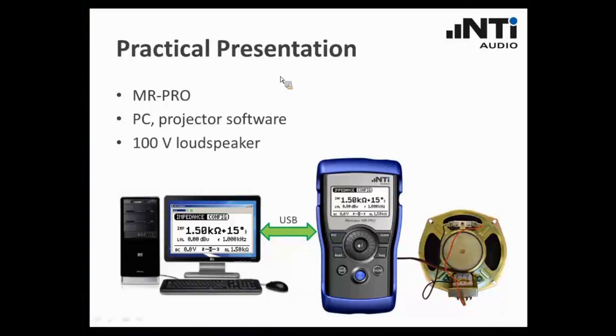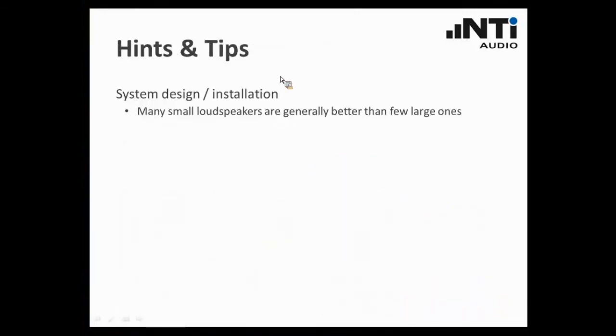I would like to provide you some hints and tips. The first one is when you design or install a system, there is a rule of thumb. Generally, it is recommended to install many small loudspeakers rather than few large ones. The reason is very simple. With a better distribution of small loudspeakers, you usually get a more homogeneous sound field in your venue, instead of having just three or four large and loud loudspeakers. They are more inhomogeneous in the sound field, and that has a negative impact on the speech intelligibility. So realizing a system with a good speech intelligibility would rather require a larger number of small loudspeakers.